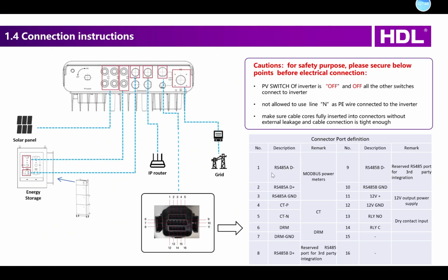And here we have very detailed specifications about this communication port with 16 pins. So here you can see for 1, 2, 3, it has Modbus power meter. In some cases, because the CT is a simple current transformer, you need a more highly accurate power meter. So you can use this one to connect a Modbus power meter instead of a CT.